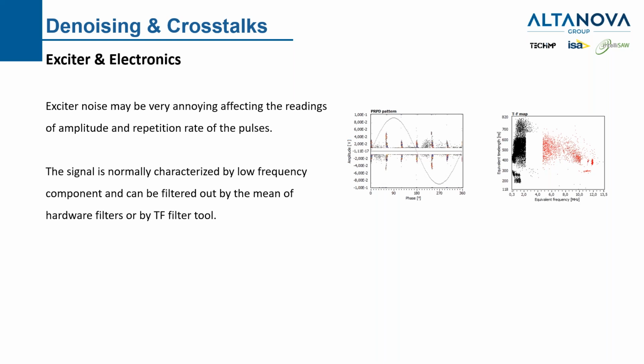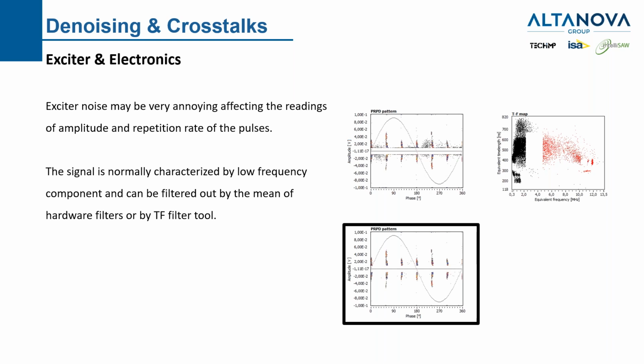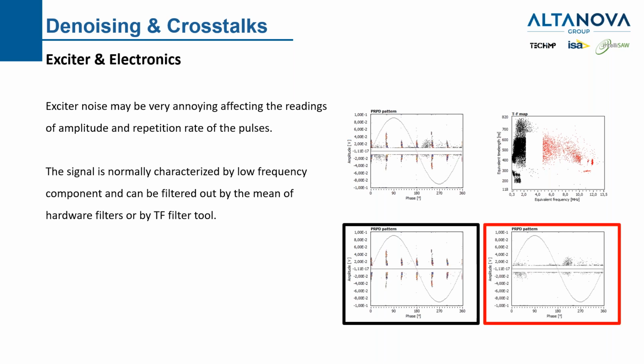So we can easily identify them, get rid of them and separate the sources with, for example, the TF-map technology that will be explained a few slides ahead. Thanks to this time frequency map separation, we can identify properly on the black cluster the exciter noise, and on the red cluster the PD phenomena together with the background noise. We can then further investigate this second PRPD pattern.